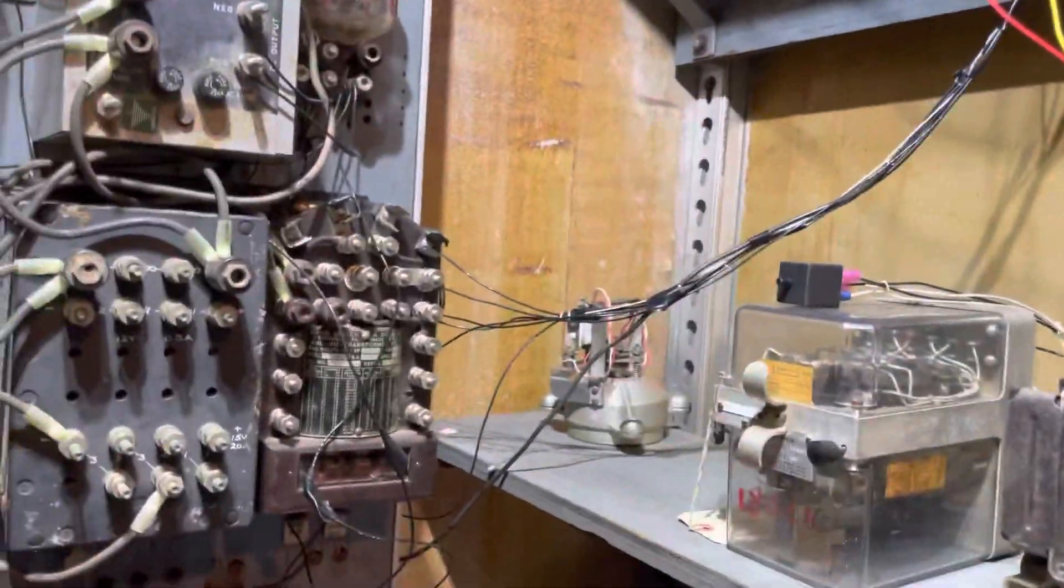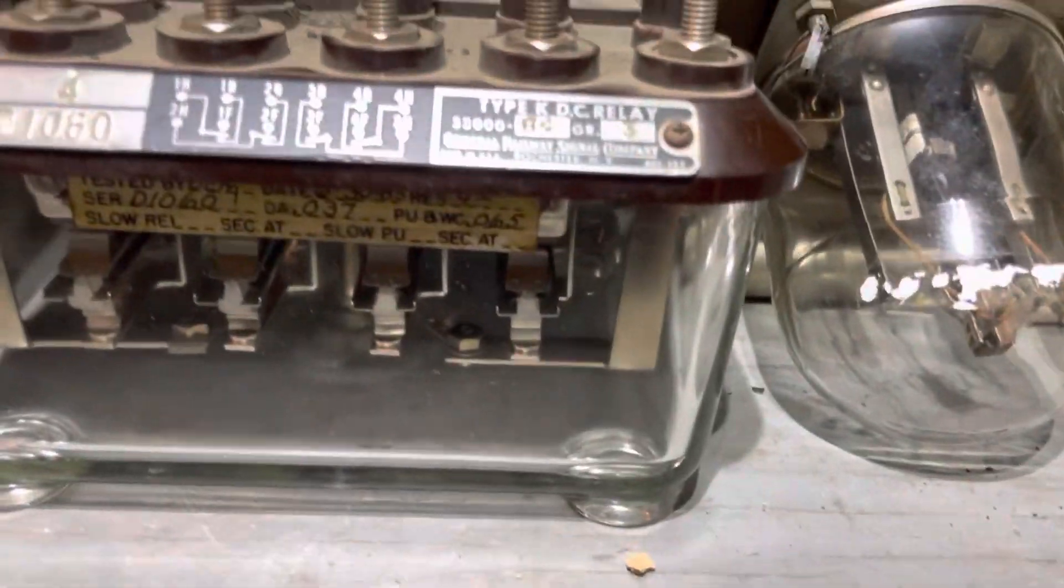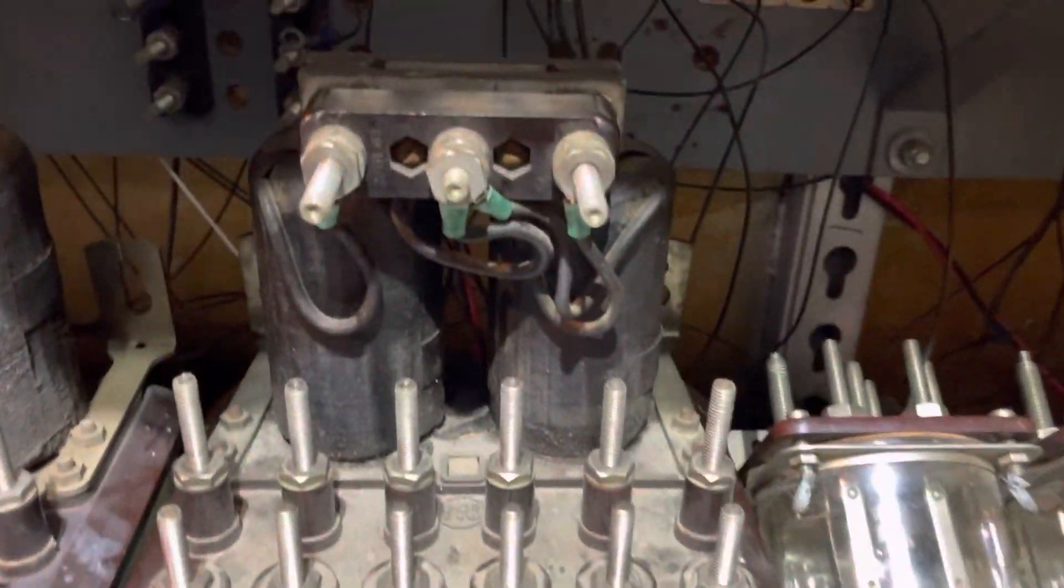Alright, we're going to be replacing this relay here. It's a six-contact relay, and I'm only using one set of contacts, so it's unnecessary. We're going to be replacing it with this equivalent four-contact relay.